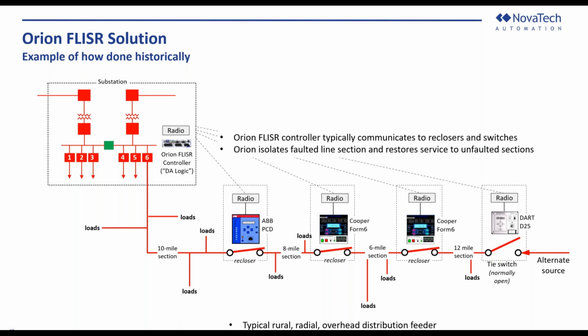As you can see, the feeder 6 is feeding various different loads and is able to talk over radio or fiber, whatever communication medium you use, and is able to generally reduce the time to cut through the overall FLISR scheme and isolate the fault and restore as quickly as possible. That's the overall FLISR concept, and this is how it's been done historically.